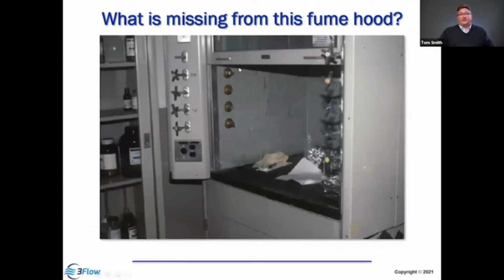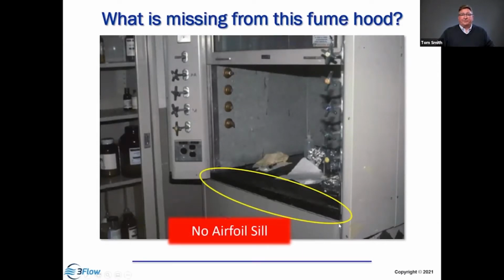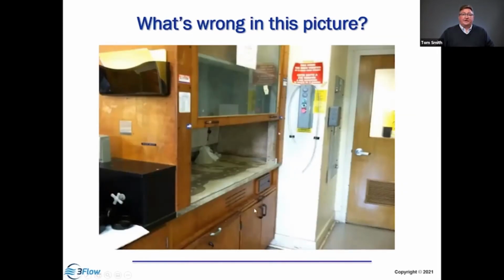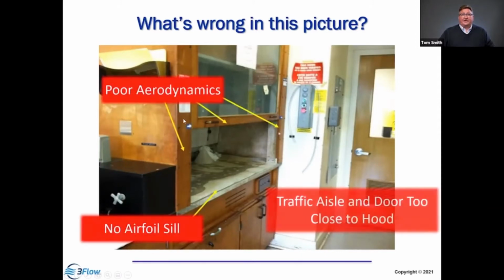For example, what is this hood missing? If we know the components of the hood, we would identify that it's missing an airfoil sill, a very important element to the capability of the hood to contain. It doesn't matter what the face velocity is if it's missing a vital component. We take a look at another hood. Clearly you see the missing airfoil sill, but what other factors do we have here? Well, the hood's made out of wood, for one. It's rectangular in shape. It doesn't have any aerodynamic entries, and it's right next to a door and a traffic aisle. So people walking by the hood could create a cross draft and pull materials out of the hood. So these are factors that could influence the containment.